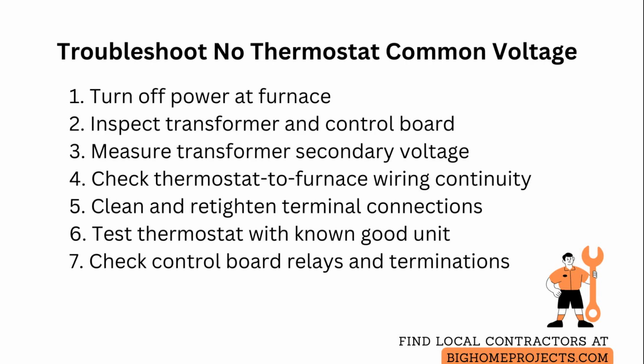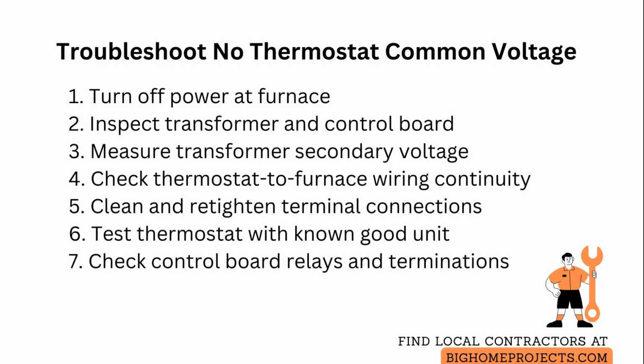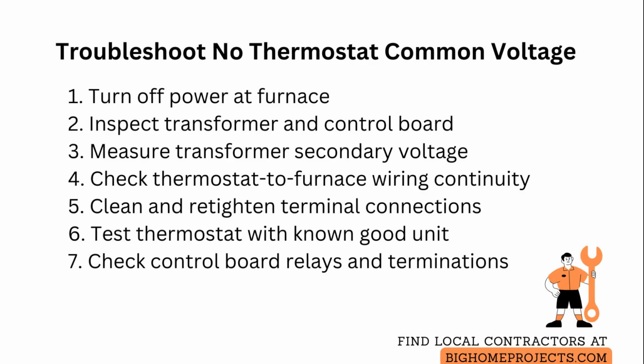Finally, check the control board logic for stuck relays or a failed common termination point. Some boards have fused common traces or modular connectors that fail and will necessitate board repair or replacement.